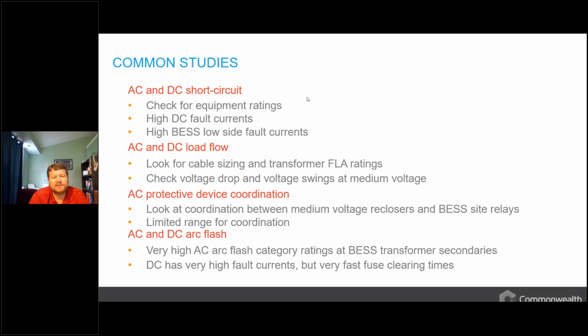We look at the AC and the DC short circuit studies when it comes to BESS applications. What we're really trying to find out with short circuit studies is making sure that the equipment is rated for the fault currents that are expected for a battery. On the AC side, it's important. On the DC side, we're seeing some challenges there, and we'll talk about that shortly.